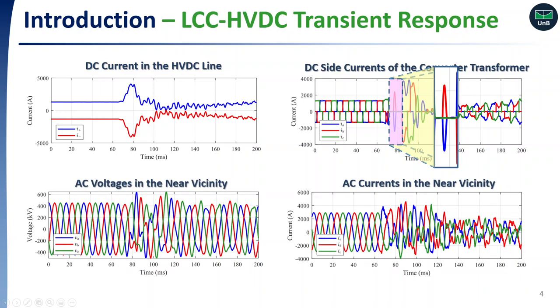These are the AC voltage and current in the near vicinity. It can be seen that the transient response of the LCC link leads to widely distorted AC waveforms, mainly during commutation failures. Therefore, an essential question arises: how do phasor-based protection relays perform in the case of distorted waveforms? In order to answer this question, we must revisit some essential concepts of the phasor estimation process implemented in commercially available relays.